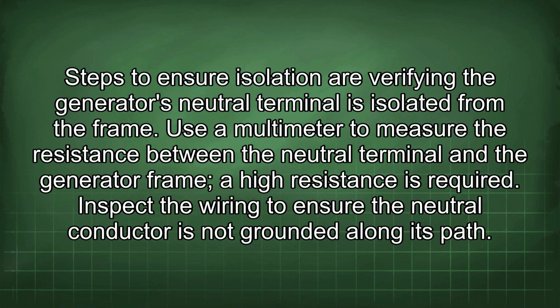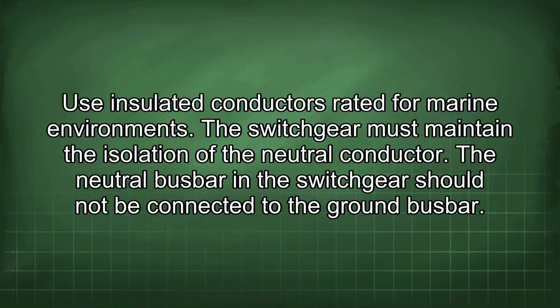Steps to ensure isolation are verifying the generator's neutral terminal is isolated from the frame. Use a multimeter to measure the resistance between the neutral terminal and the generator frame. A high resistance is required. Inspect the wiring to ensure the neutral conductor is not grounded along its path. Use insulated conductors rated for marine environments.